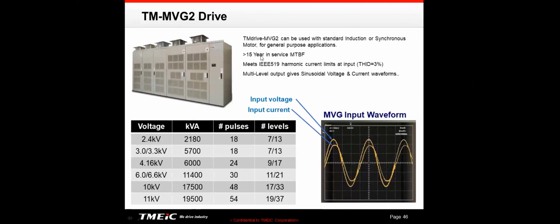We will talk about this in a moment, but when we talked about low voltage versus medium voltage, reliability was a huge concern. Medium voltage drives are much, much, much more reliable than low voltage drives. Some medium voltage drives are much better than others. If you look at a drive in the steel industry, for instance, when we had an outage, we'd lose $100,000 an hour. So we just can't afford that.